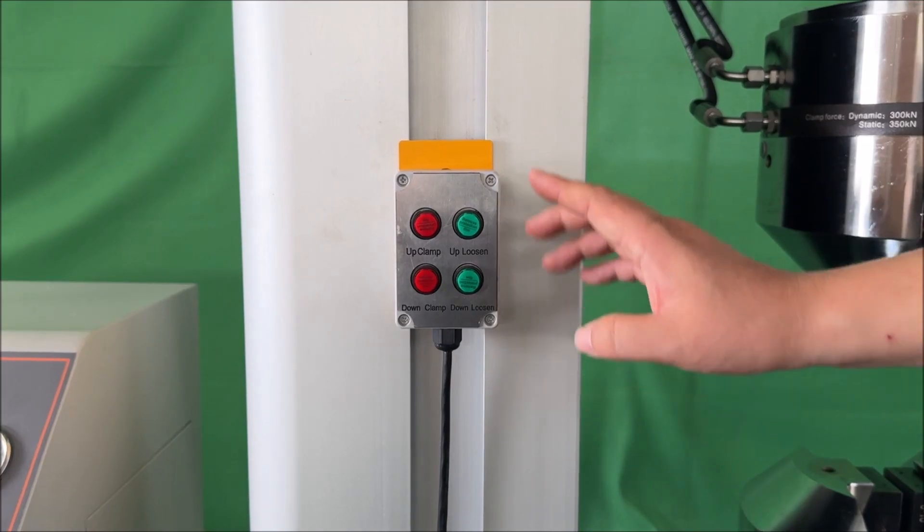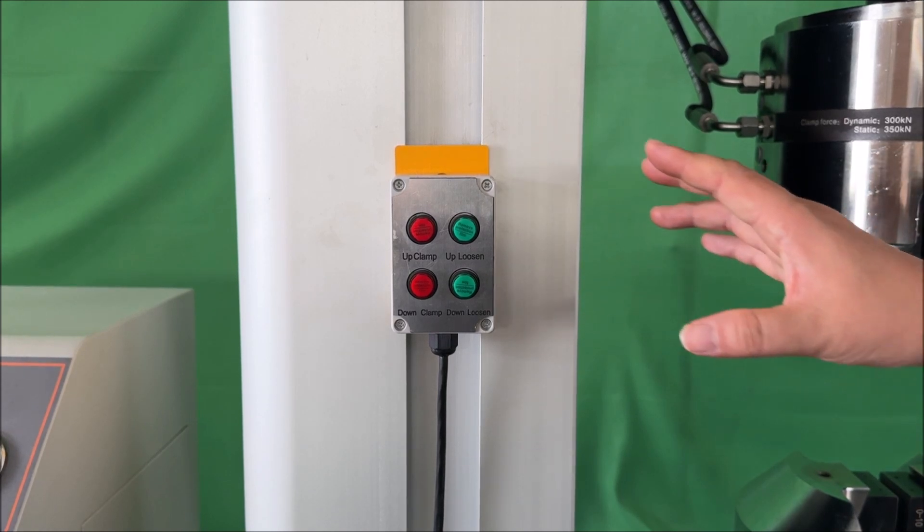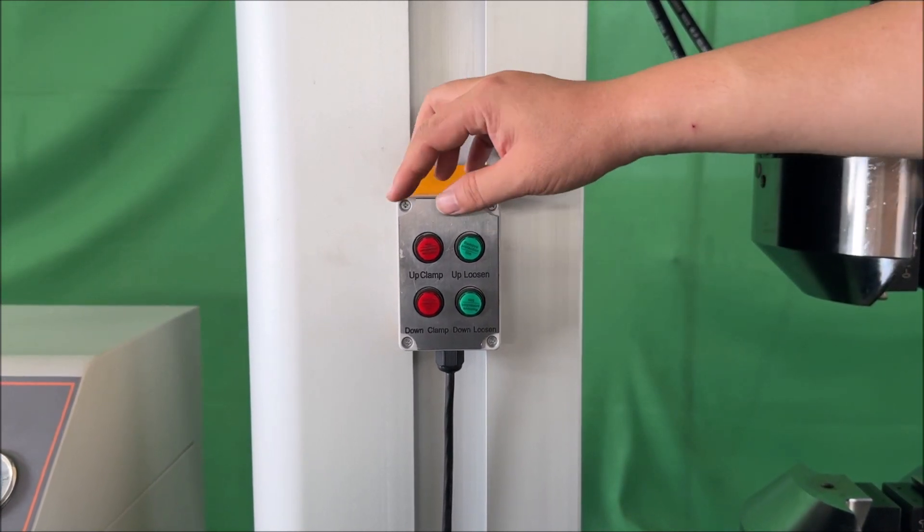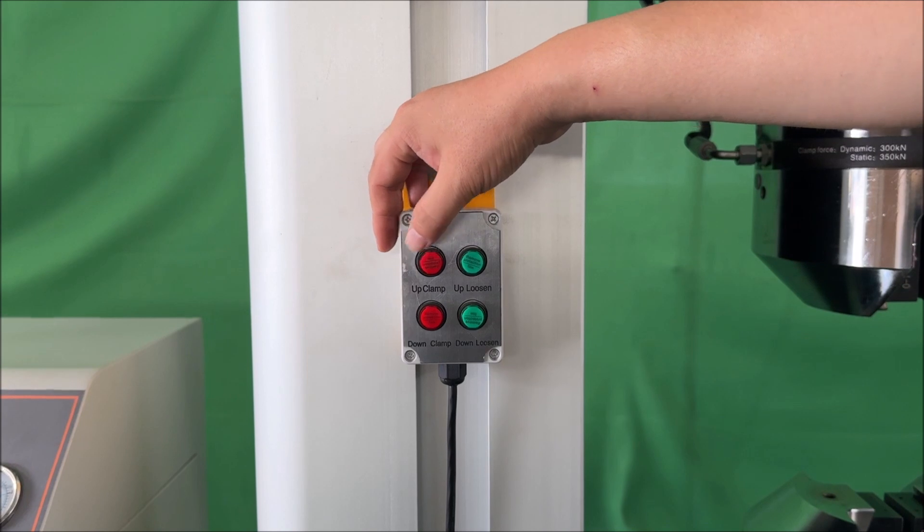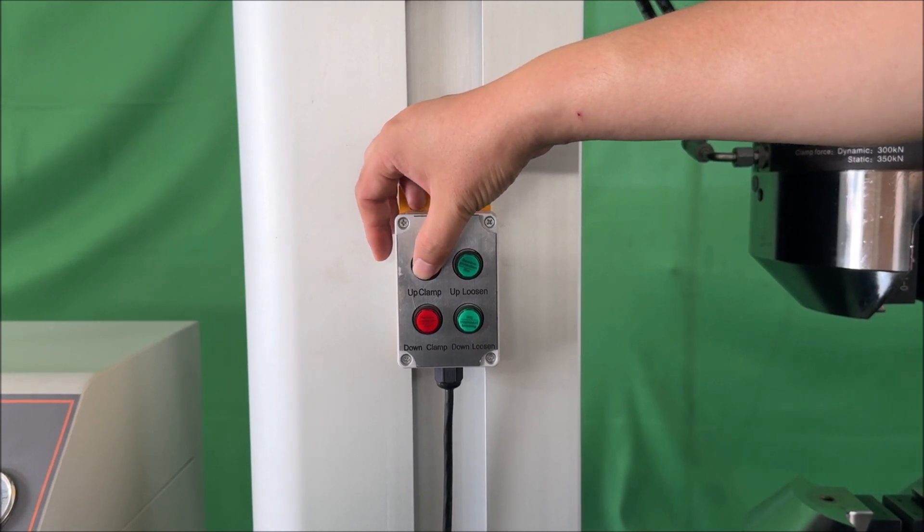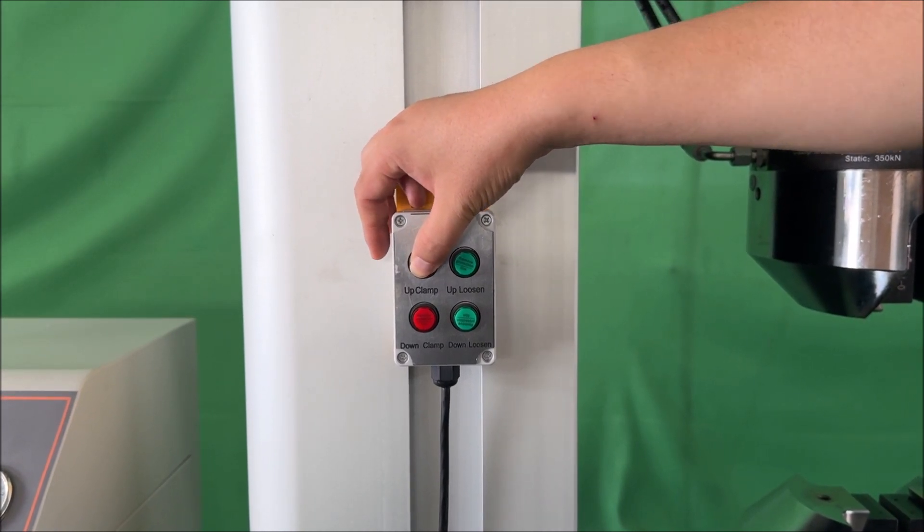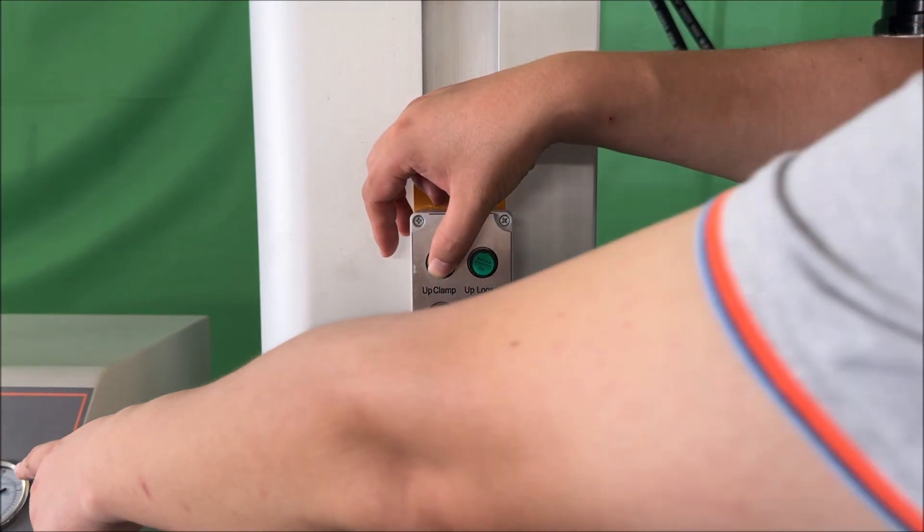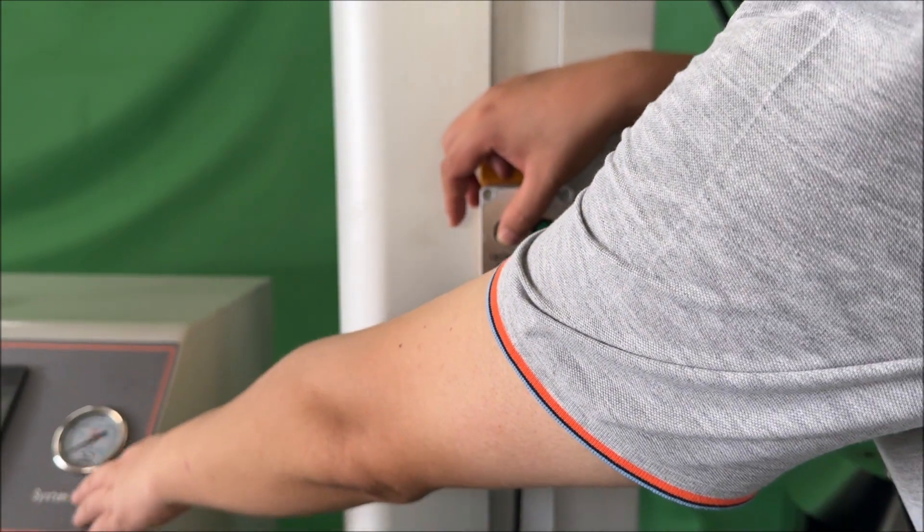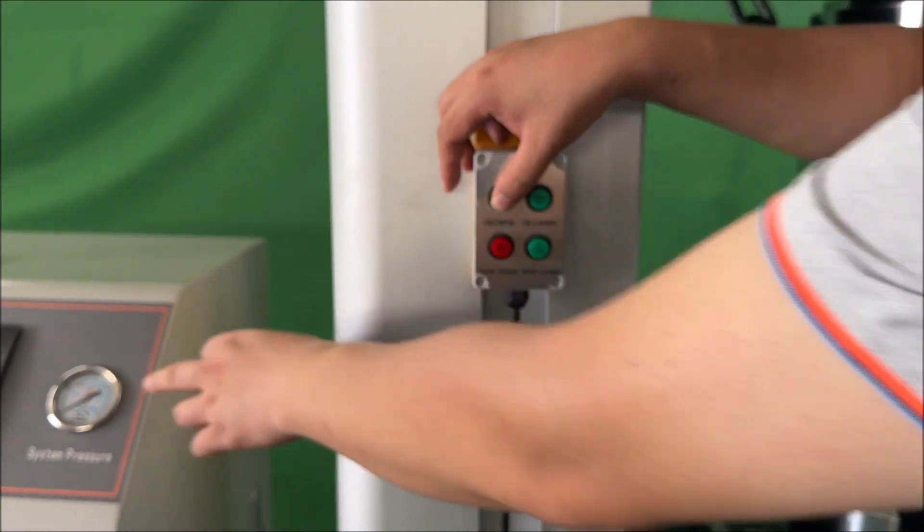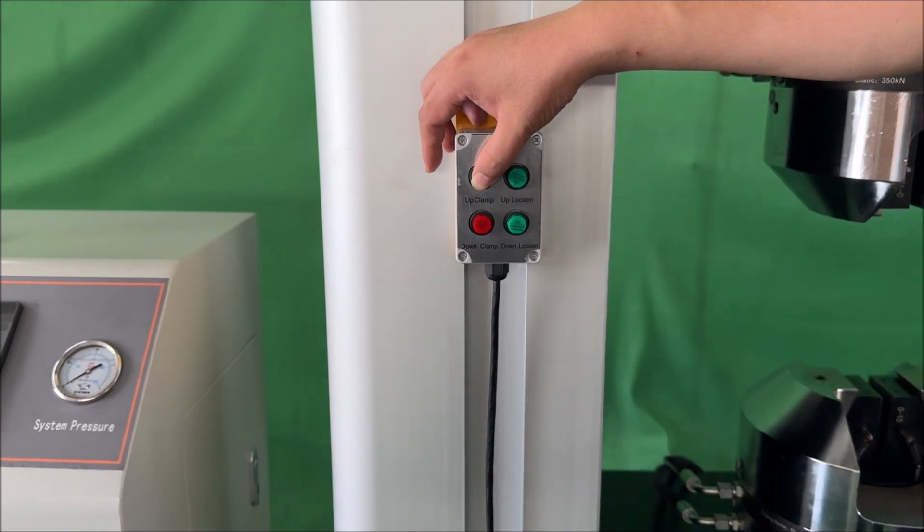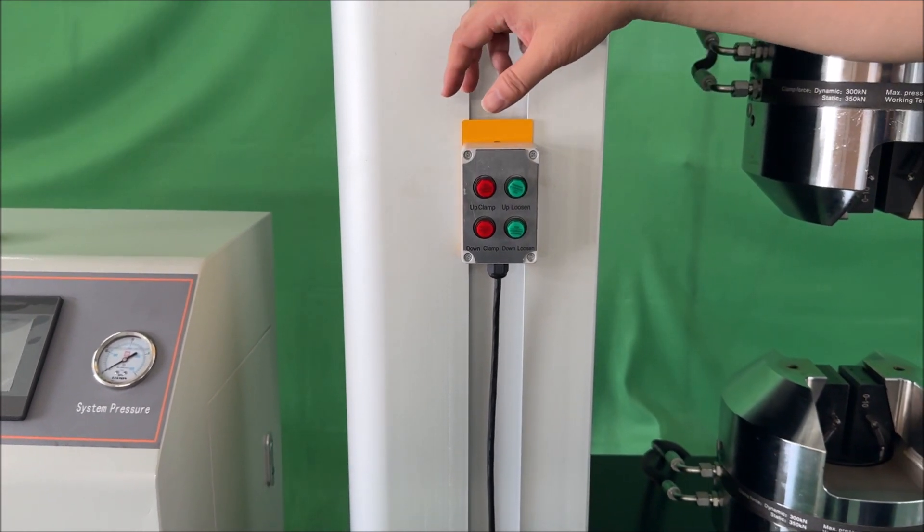When using the manual hand control box to clamp and loosen, press a button, for example, upper clamp, and monitor the system pressure. Once the pressure reaches 2 megapascals, release the button. The grips will gradually move toward the indicated target pressure.